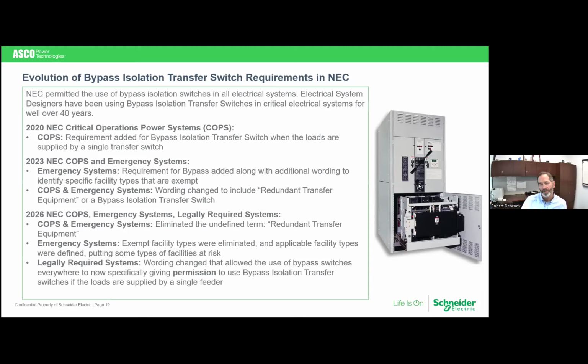Let me give you a couple examples. In 2014, for the first time, critical operations power systems required that if you have a single source of power, you will have a connection for a temporary source of power. Great idea - they must have had a problem at some critical facility where the backup generator didn't work and there was no easy way to connect an alternate power source. Then in 2017 they said, that was such a great idea for COPS, we ought to put it in there for emergency systems too.